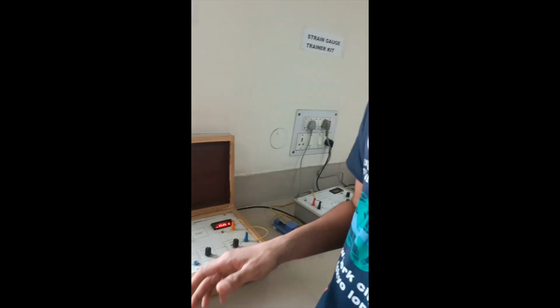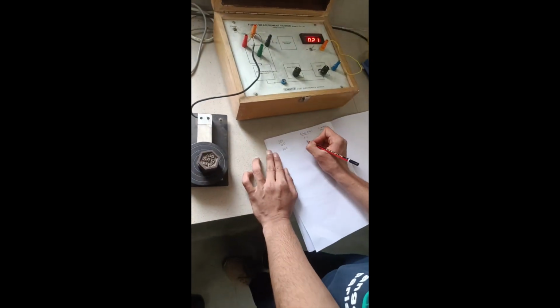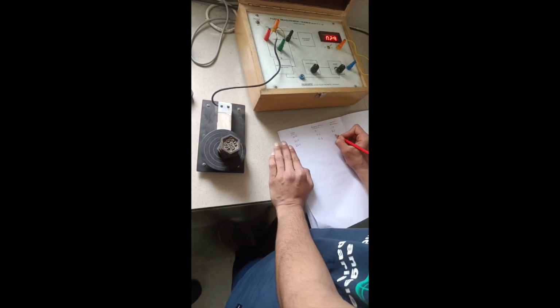To do this experiment, we should apply the force gradually, from 0 grams to 100 grams, then increasing each weight by 100 more grams until we reach 1 kg. Then we will note the kg readings, and then we'll unload the cell. We'll note the readings further. We have now recorded the readings for the loading part.